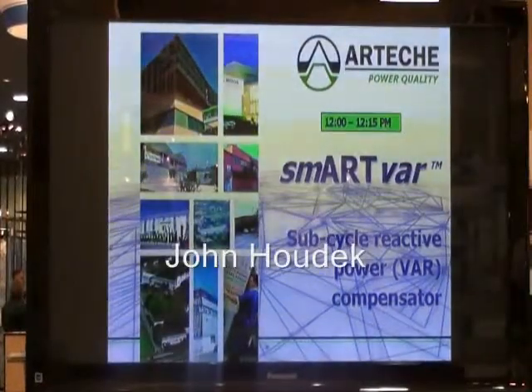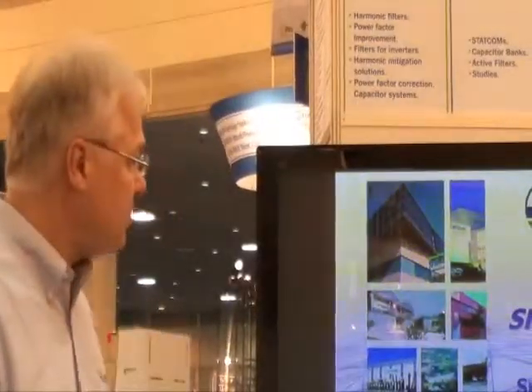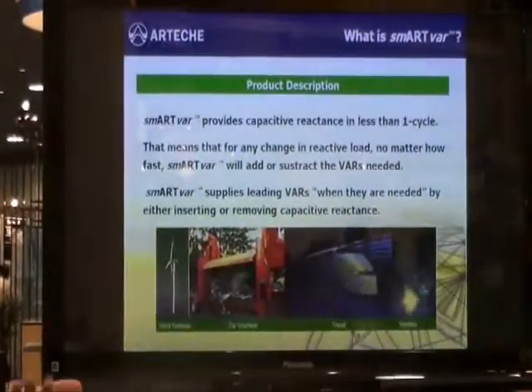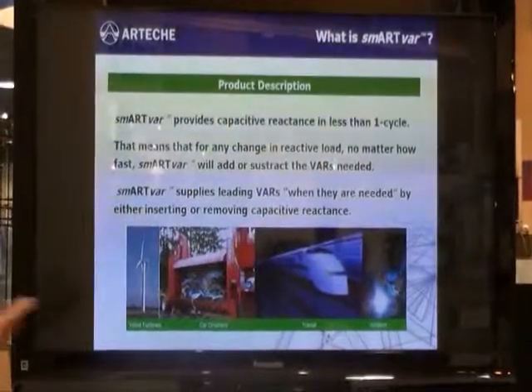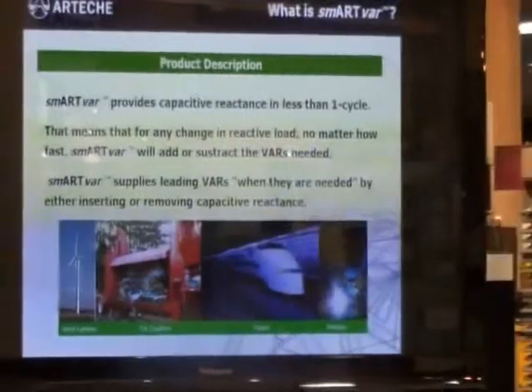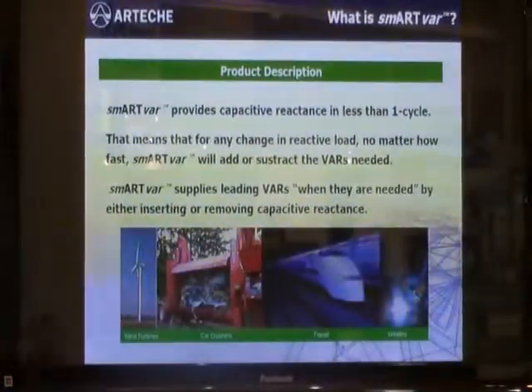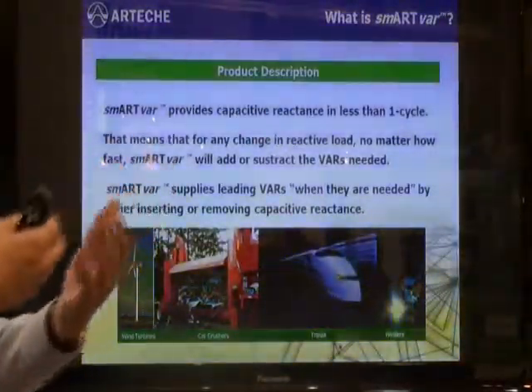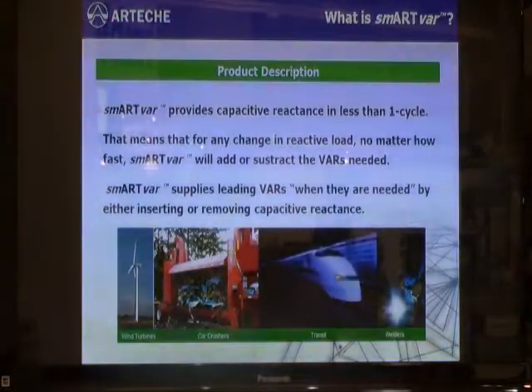The SmartVar product from Arteche is our answer to sub-cycle reactive compensation. The SmartVar is intended to provide reactive compensation to a system in less than one cycle. It's a very rapid switching of capacitance, and it can compensate for a dynamic change in reactive loads such as motors in a facility. It will either add reactive vars to a power system for compensation or remove those vars when they are not needed.